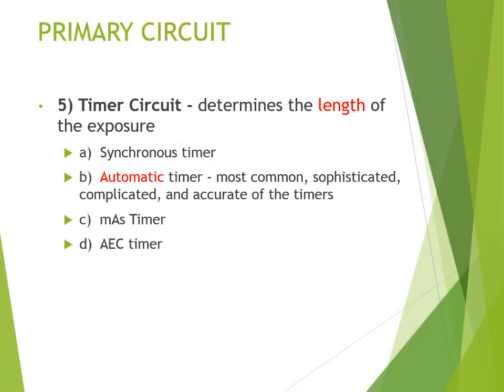The timer circuit determines the length of the exposure. We have the synchronous timer, which was used in fractions for single phase units. The automatic timer is the most common, sophisticated, and complicated and accurate of the timers, and it's the one that's most commonly used, as I said. The mAs timer has a combination of MA and time together, so it just has mAs. And then there's the AEC timer, which we'll talk about in a separate lesson, automatic exposure control.